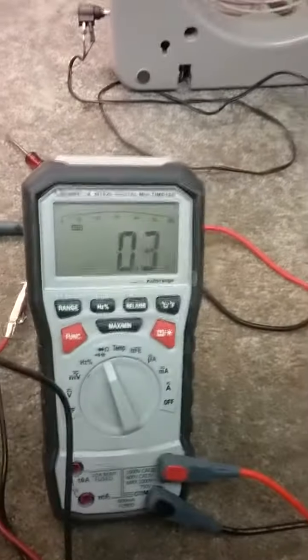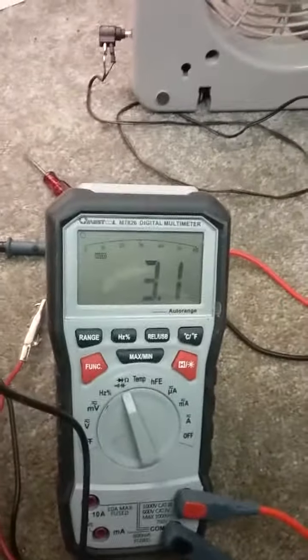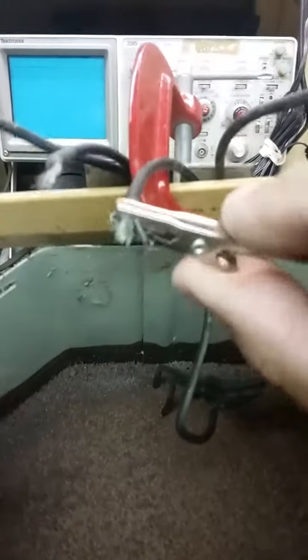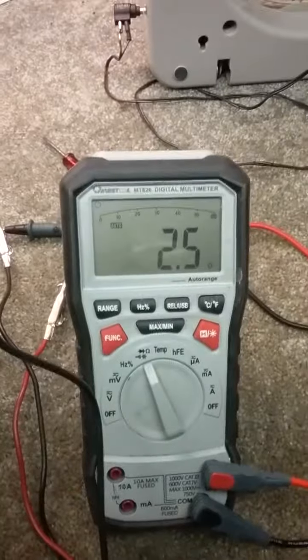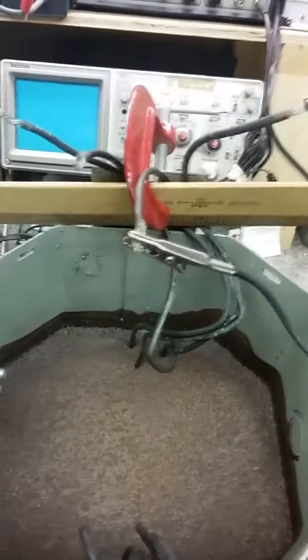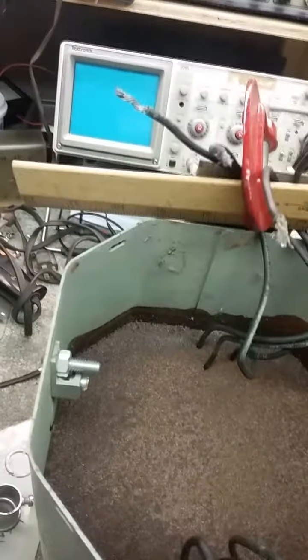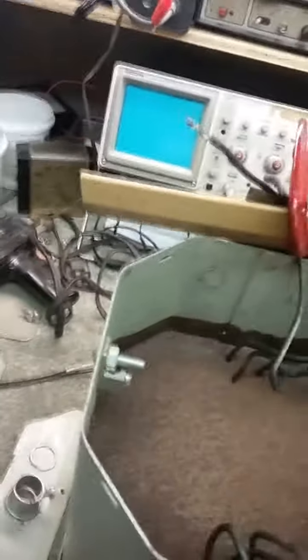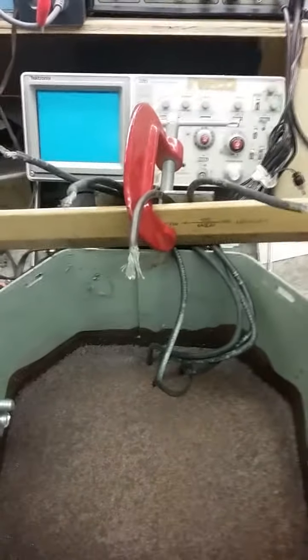Okay, connecting coil 2, and we got 3.1 ohms. The resistance is so low that just moving the connectors around is going to change the value, see. So they're about the same, they're matched. And there's no short because both coils are good, and there's no resistance between them. There's no leakage between those two coils on the primary side. We will check also across primary to secondary. But the next thing we want to do is check the first coil on the secondary. So we'll hook that up.